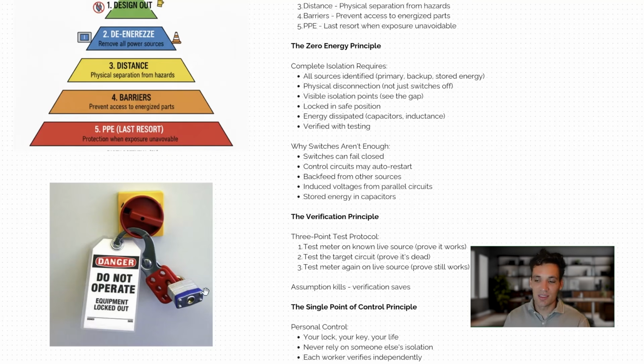Why is that critical? Because say there's some confusion, some miscommunication. Someone thinks the circuit is safe to energize again. They don't realize that this person is still working and in contact with the circuit. Someone could just go and flick the circuit on. With it actually being physically locked off with the person working on the circuit having a key, it's impossible to happen. Someone can't go and simply switch it on because it's locked in the off position with a personal padlock. The person doing the work has the key to that padlock.